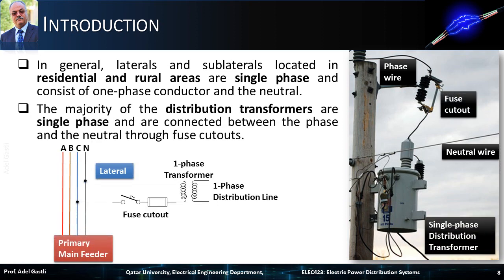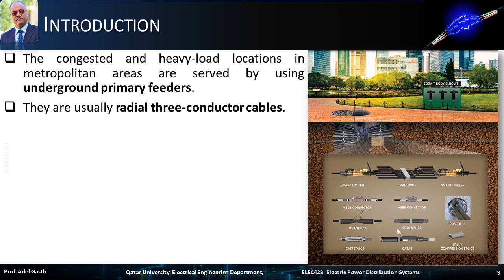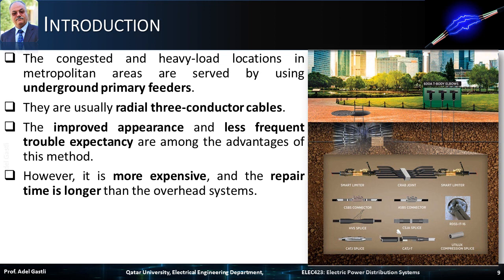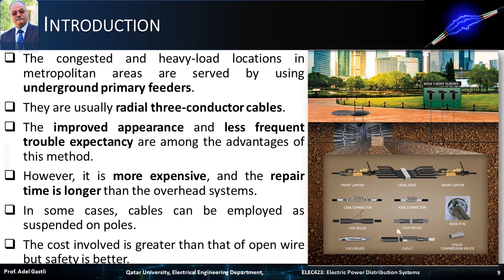The majority of the distribution transformers are single-phase, and are connected between the phase and the neutral through fuse cutouts. The congested and heavy load locations in metropolitan areas are served by using underground primary feeders. They are usually radial three-conductor cables. The improved appearance and less frequent trouble expectancy are among the advantages of this method. However, it is more expensive and the repair time is longer than the overhead systems. In some cases, cables can be employed as suspended on poles. The cost involved is greater than that of open wire, but safety is better.